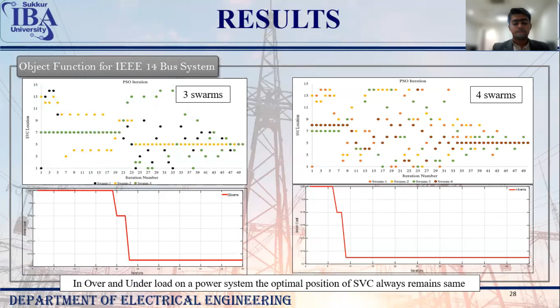The optimal placement of SVC in the IEEE 14 bus system. We have already designed the IEEE 14 bus system in MATLAB, and we have already calculated that the best allocation for the position of SVC is bus number 5. So we start placing it on bus number 5 for minimization of losses. In this case, the load is added up to 59, and the power losses are 13.7 kilowatt, which are given as input to the PI controller. The graph below shows that the losses get minimized with the help of a PI controller and reach steady state at 13.7 kilowatt.